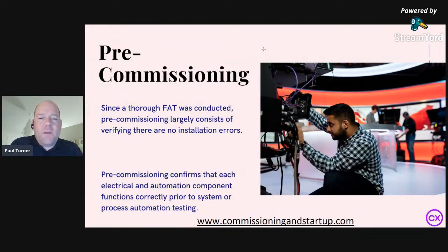So following mechanical completion, we move into pre-commissioning. Since the FAT was conducted very thoroughly, pre-commissioning will largely consist of verifying that there are no installation errors. Through pre-commissioning, this is really when the loop checks will be completed. Through the loop checks, you'll be verifying from the cubicle that the cabling is correct, that you can communicate with the end device, and that you're getting the right control and monitoring of that end device.